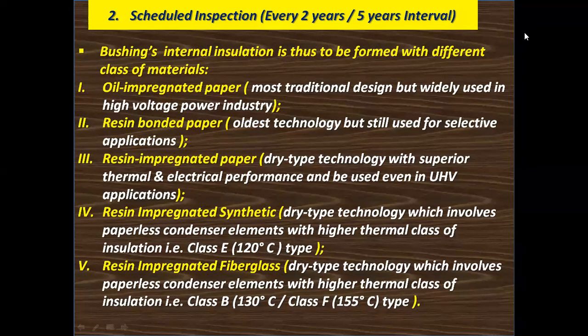Number three, resin impregnated paper. Dry type technology with superior thermal and electrical performance, and used even in UHV application, that is ultra high voltage. Number four, resin impregnated synthetic bushing insulation, mainly used in dry type technology, which involves paperless condenser elements with higher thermal class of insulation, that is class E, 120 degrees centigrade type.